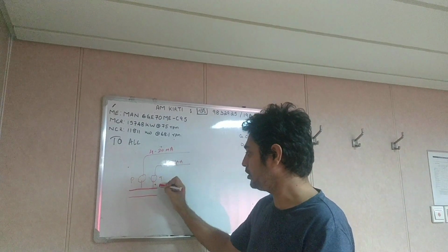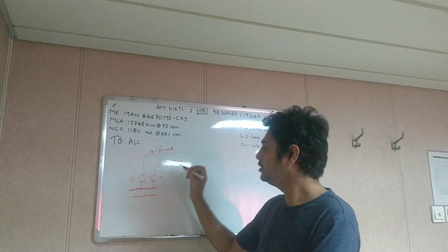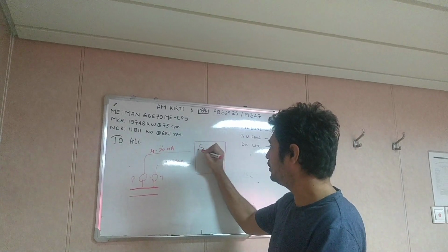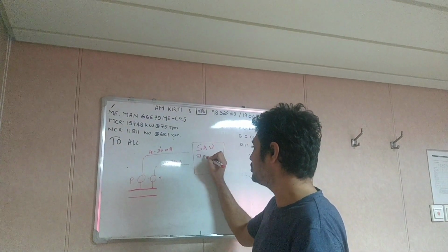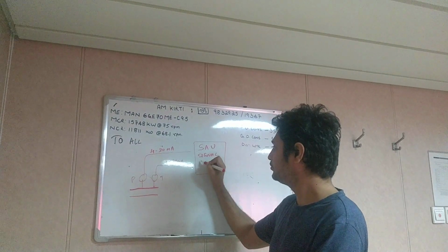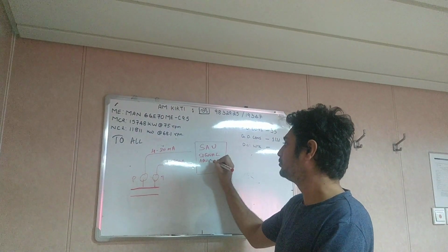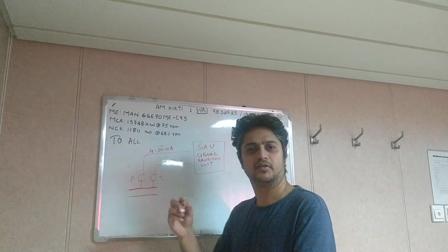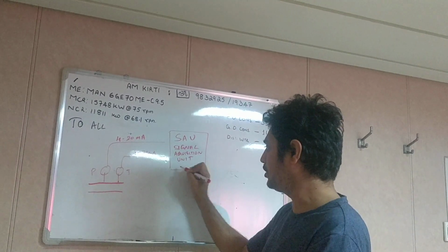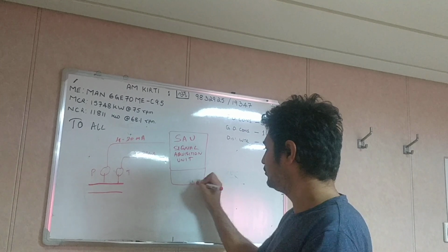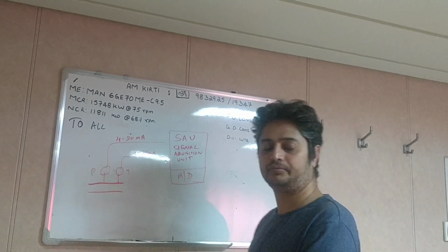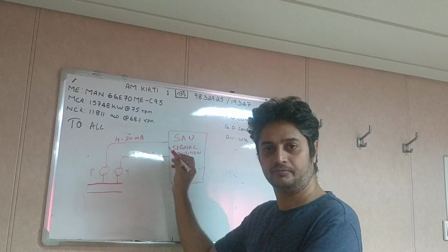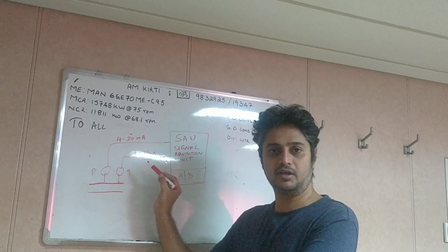So this signal, whatever the sensor output is, is transmitted to the SAU, Signal Acquisition Unit. Basically, in the Signal Acquisition Unit there will be an analog to digital converter. Whatever signal is coming here, these are all analog signals. The sensor's 4 to 20 milliamp signal is analog.